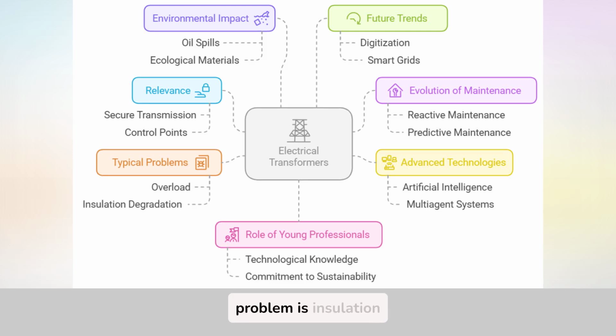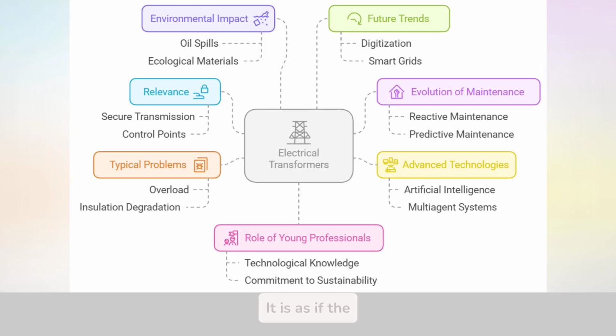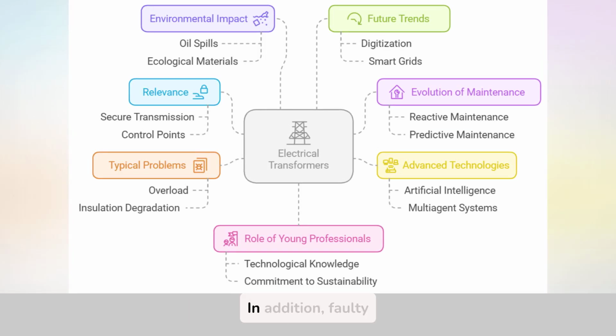Another frequent problem is insulation degradation due to humidity, high temperatures, and contaminants, which increase the risk of short circuits. It is as if the transformer's shield weakens over time. In addition, faulty cooling systems and contamination can cause overheating and breakdowns.